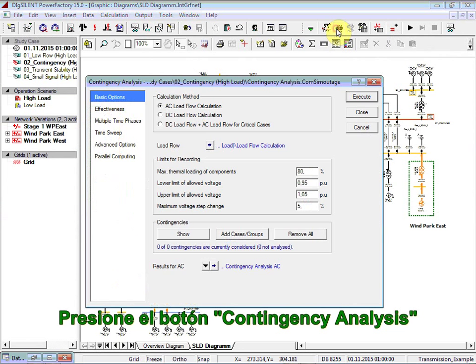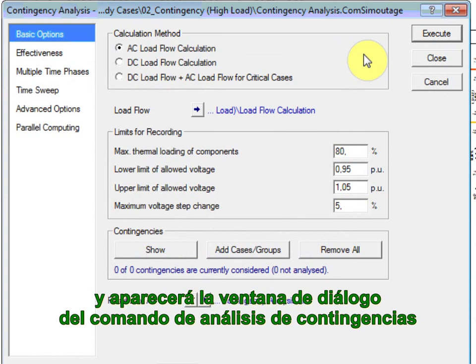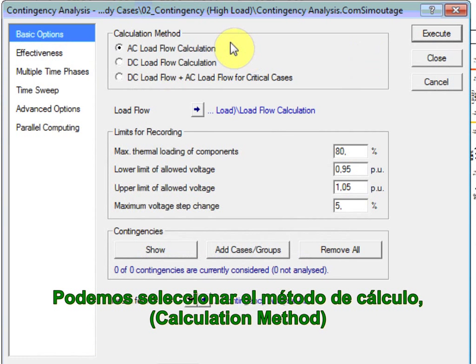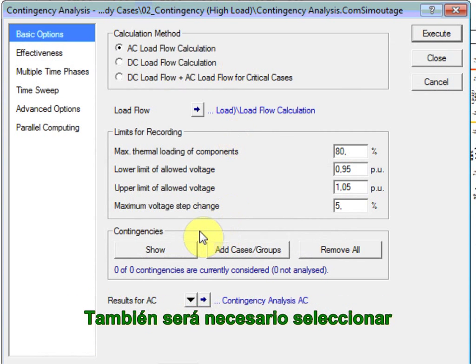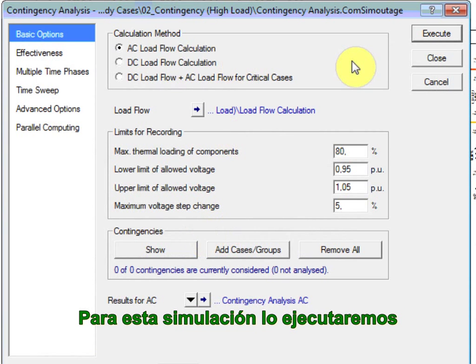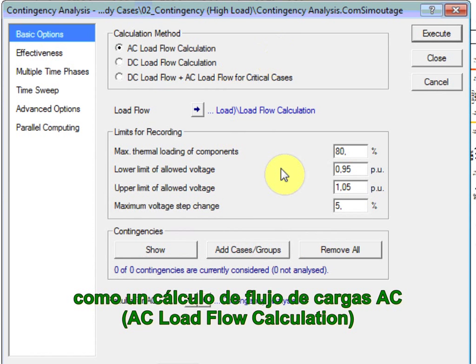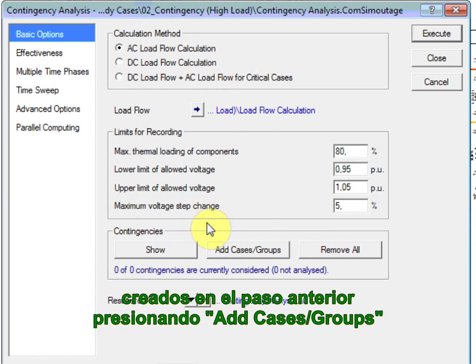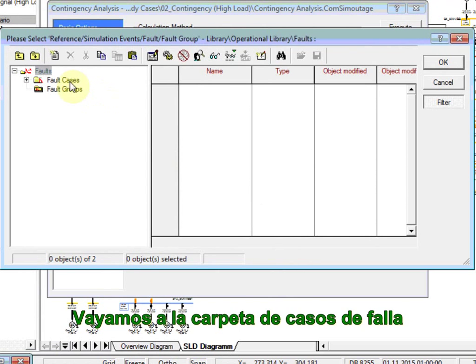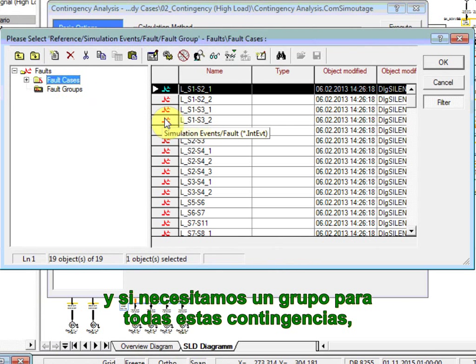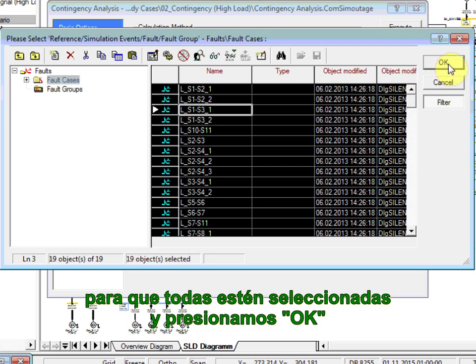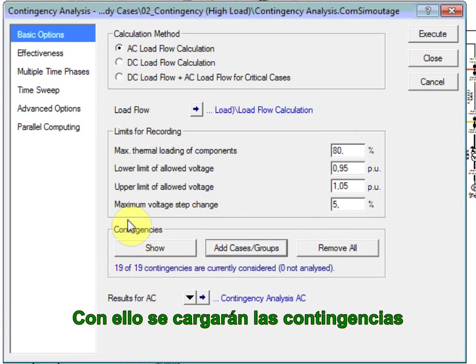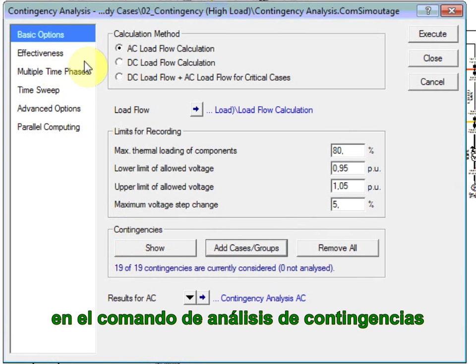Click on the contingency analysis button so that a contingency analysis command dialog appears. Here we can select the calculation method and the limits for recording. It will also be necessary to select the contingencies to be simulated. For this simulation, we will run it as an AC load flow calculation. We will then define the contingencies created in the previous step by clicking on add cases groups. We go to the fault cases folder and select all contingencies using Ctrl-A, then press OK. The contingencies will then be loaded into the contingency analysis command.